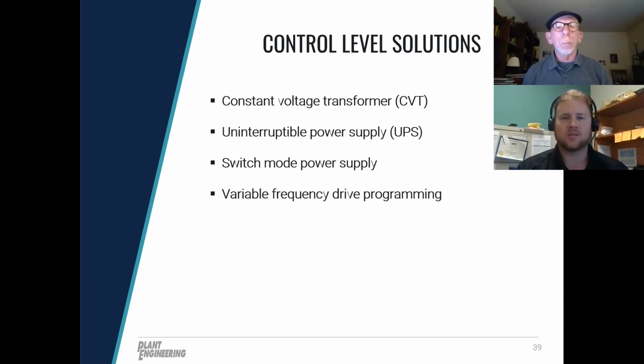Keep in mind UPSs are basically very high-tech batteries. You do need to have some maintenance program. Keep an eye on them. Your service provider may do that as well. Keep an eye on your battery cells. Also, centralized UPSs aren't really cheap, but if you're facing downtime every time you see that short duration voltage sag or transient voltage event, the large centralized UPS purchase may be well justified.